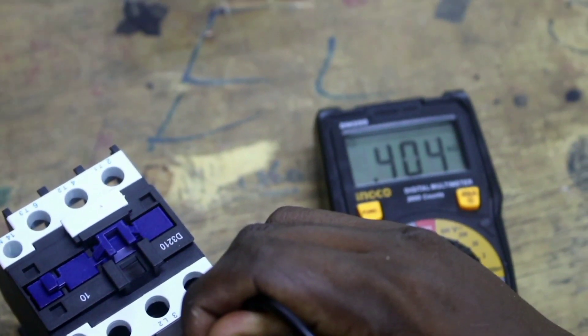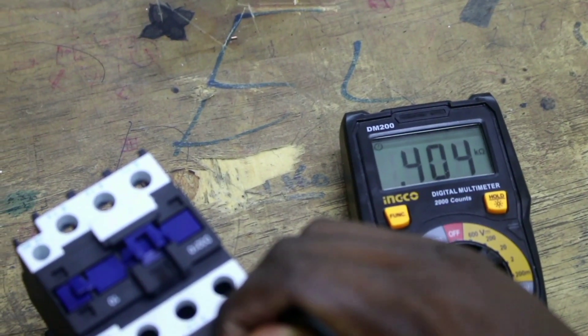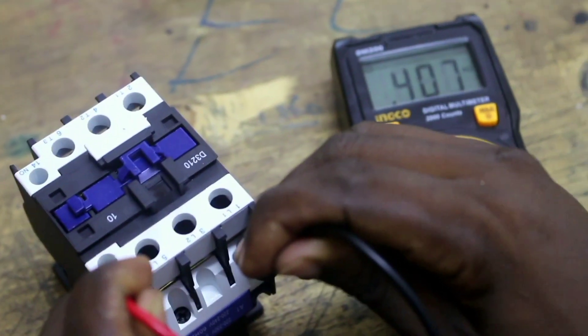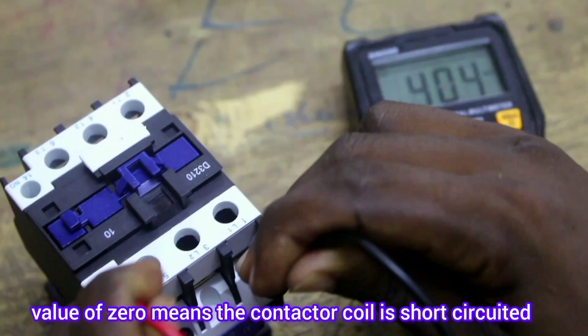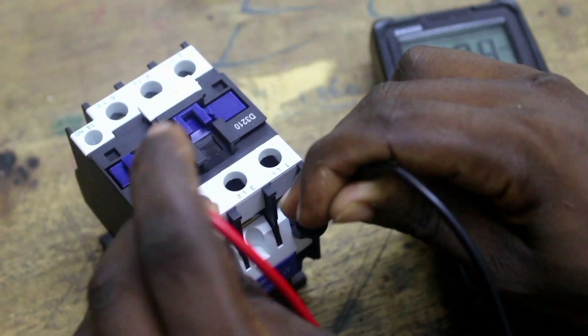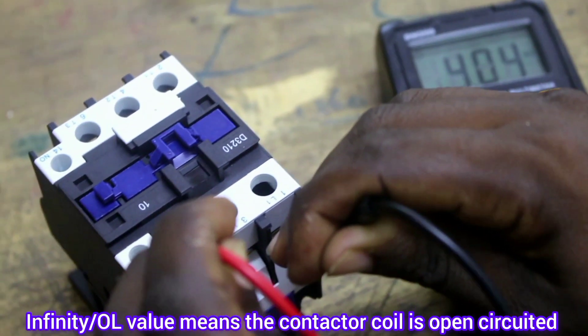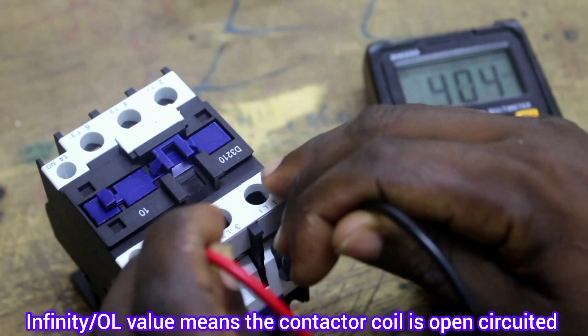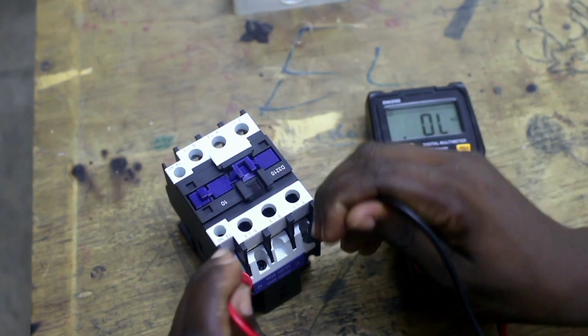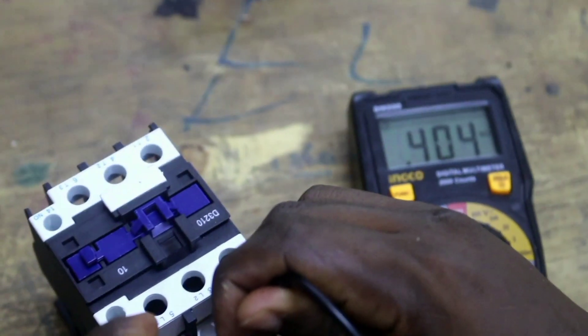Different contactors have coils with different resistances depending on the design and size of the electromagnetic contactor. If you measure between A1 and A2 and get zero, the coil is short-circuited inside — do not use that contactor. If you get infinity, what we call over limit on the multimeter, there is an open circuit in the coil; it is not continuous, so don't use it. Our contactor is okay because it reads 0.4 kilo ohms — not zero or infinity.